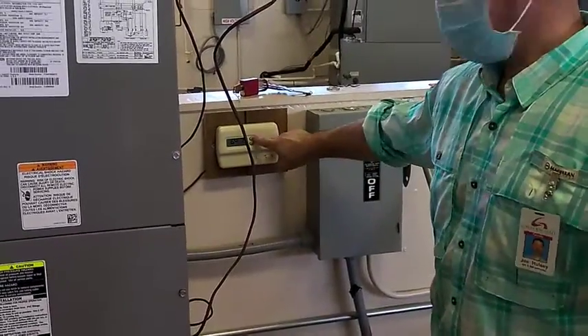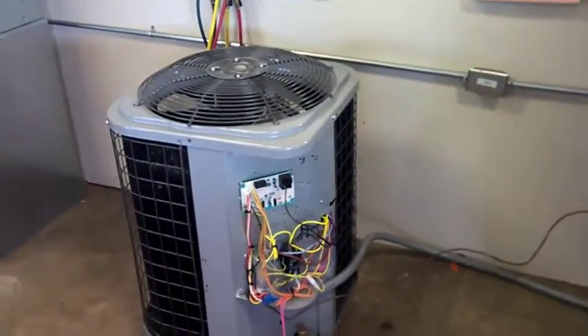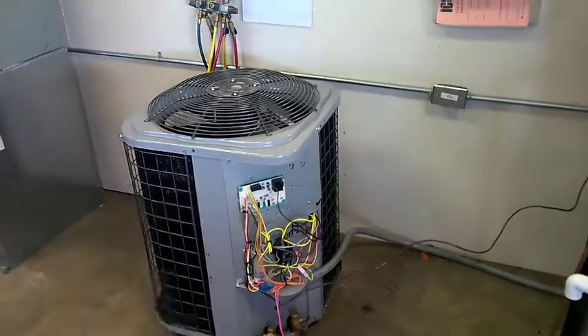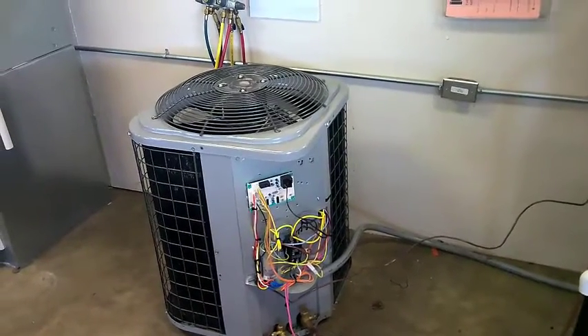Alright, now we're going to cut this thing on heat mode and let it kick on. And with that fan disconnected, it should start freezing this coil, and we can see what temperature our switch closes at.